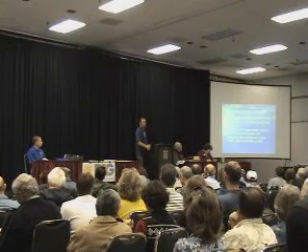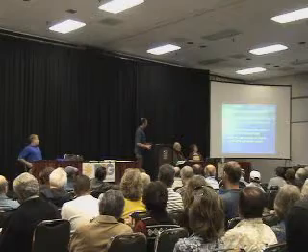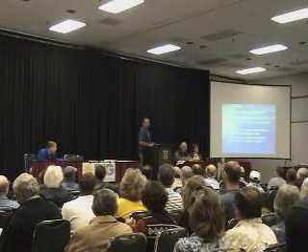Just briefly, talking about energy use and impacts: hot water is somewhere between 14 and 25 percent of the energy use in a typical home. People who heat with both gas and electric — both can be replaced with a solar hot water system. The average electric hot water heater results in about 200 pounds of coal being burned per month in order to produce the electricity. The amount of sunlight captured by a photovoltaic system and turned into electricity ranges from 8 percent to about 20 percent — the rest is either reflected or turned into heat. A solar hot water heating system can capture 70 to 80 percent of the sunlight being cast on that collector, so it's really an efficient technology.